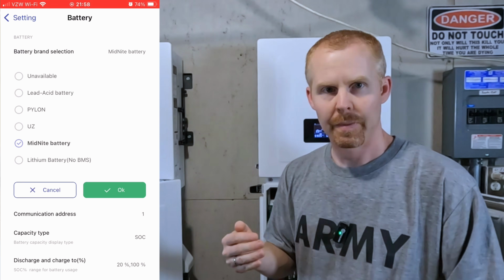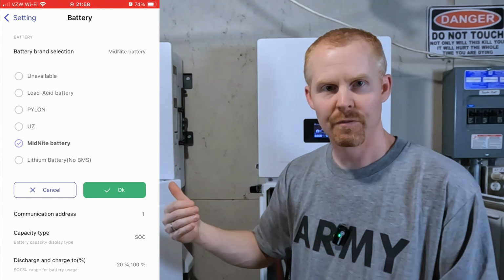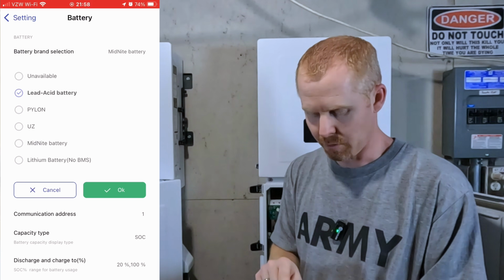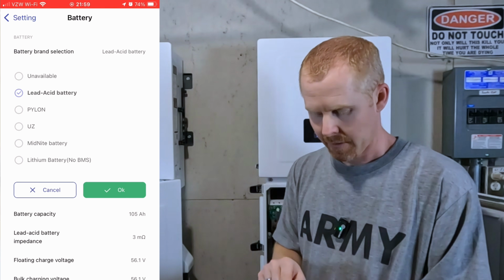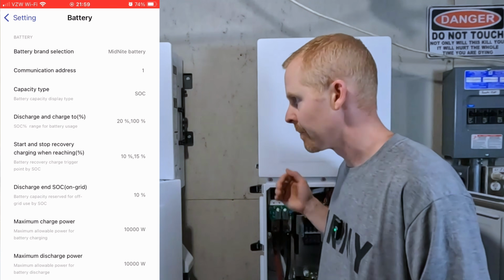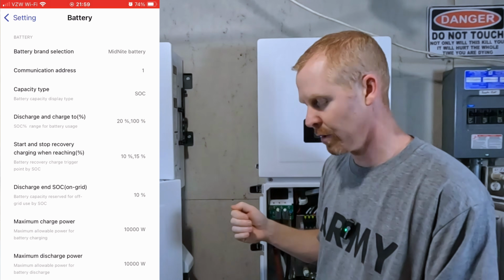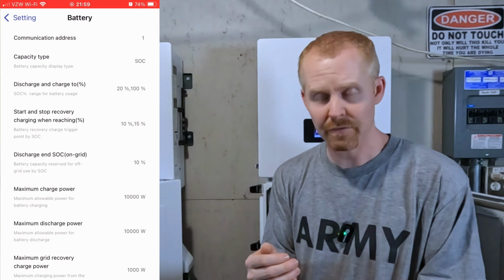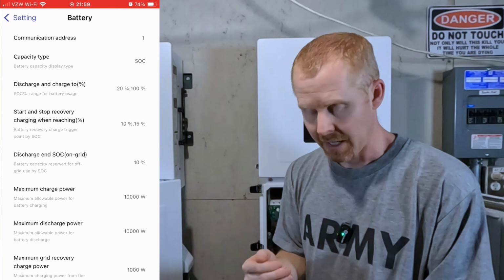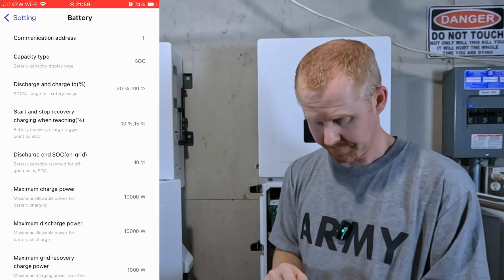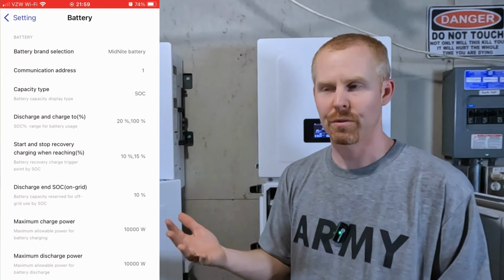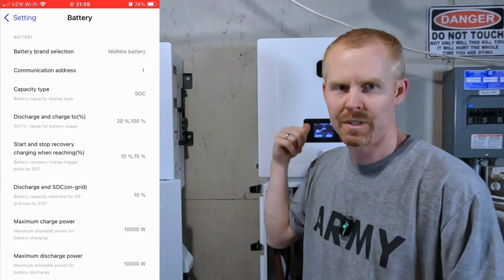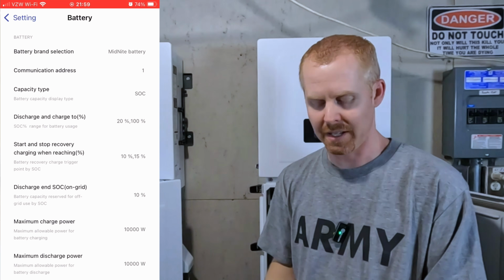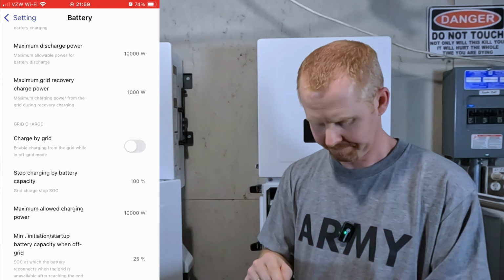Under battery, to make sure that both inverters are synced for the battery, I'm going to set it to lead acid, hit OK, and then come back to Midnite and hit OK, just to push that change over. And you might actually have to go through and configure your battery discharge settings on your slave inverter as well. Like I said, I wish that as soon as you enable it, it would take the settings from the master and just push them to the slave, but it doesn't seem to do that right now. So if we look at inverter 1 right now, we can see that it's a solar panel with a house.